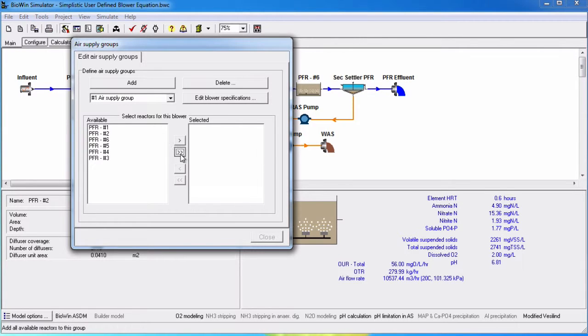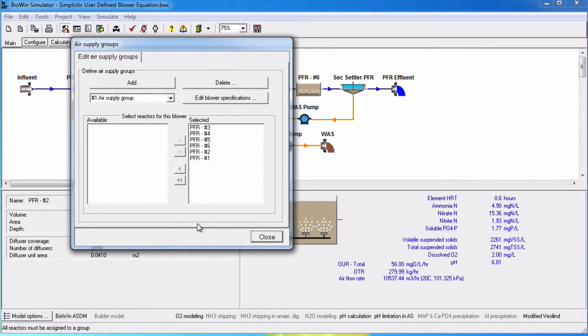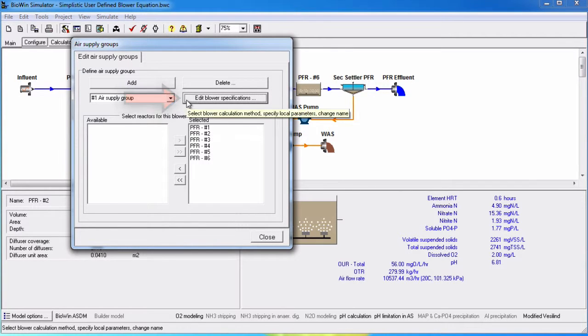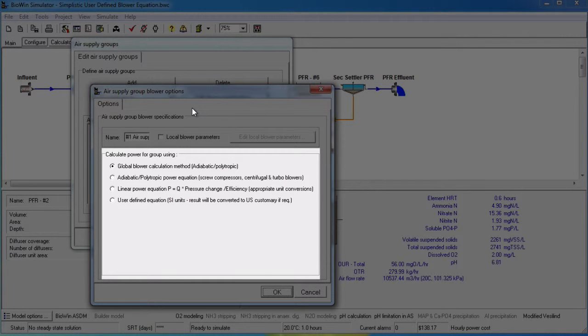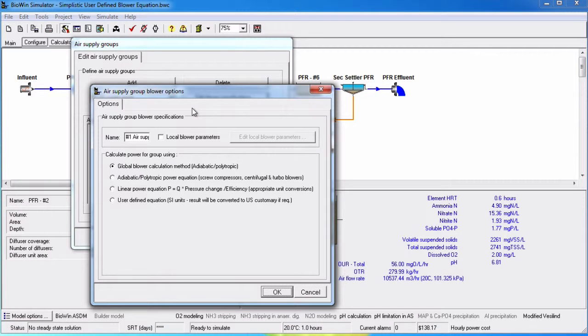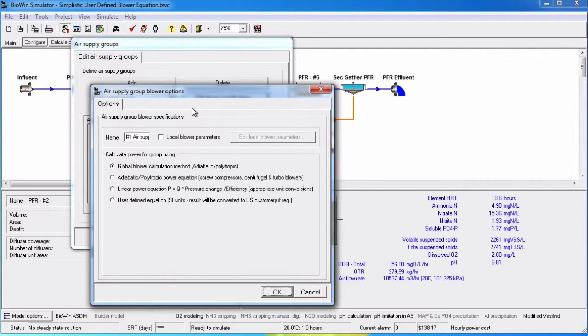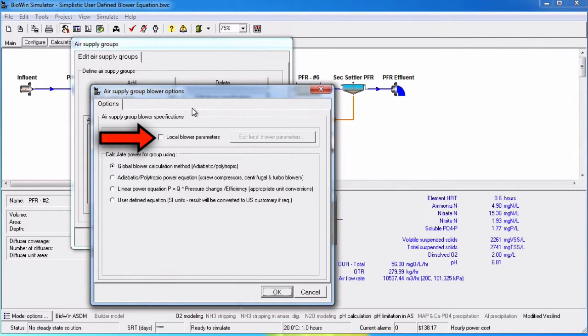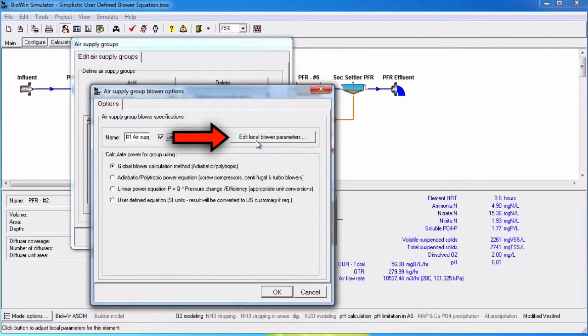If you want a blower group to have parameters that are different from the global blower parameters, or if you want to have a different calculation basis than the global method, then you can click the Edit Blower Specifications button to set local conditions for the specified air supply group in the drop list box. In the Calculate Power for Group Using Radio Button group, we can specify the method for calculating blower power. You can either use the global blower calculation method, which is specified in brackets, or choose from the other three available options. You can also specify local blower parameters for the specified air supply group by clicking on the checkbox Local Blower Parameters and clicking on the Edit Local Blower Parameters button.